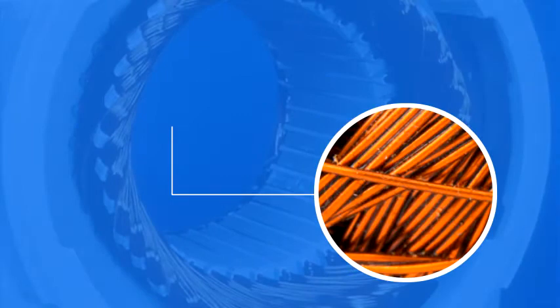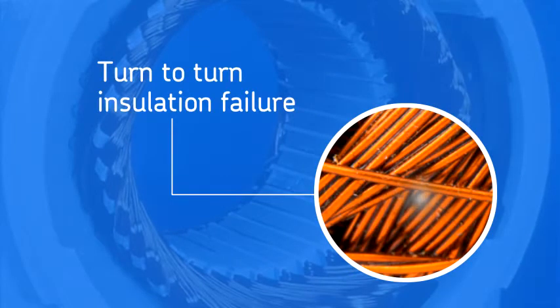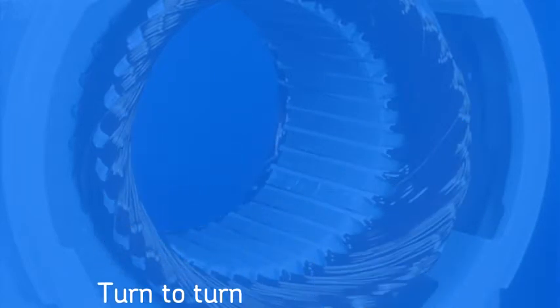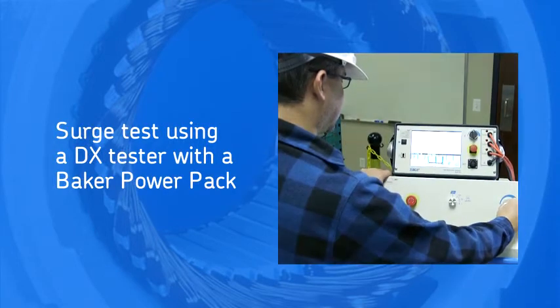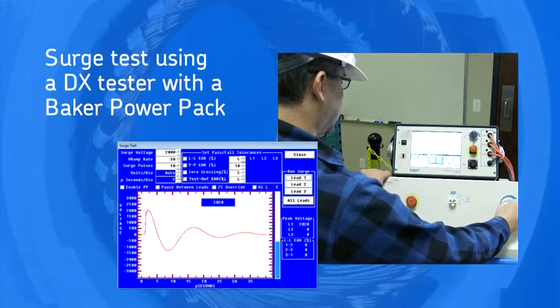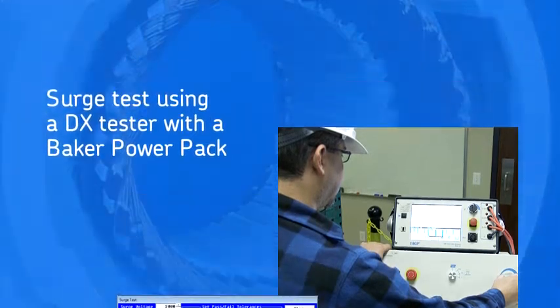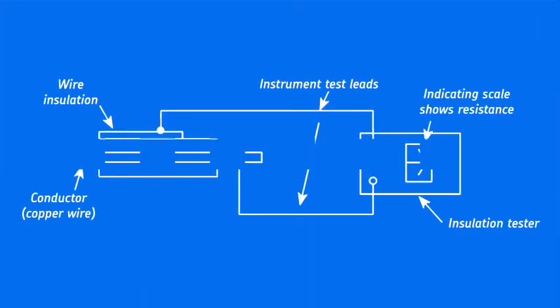The most common insulation fault is a turn-to-turn insulation failure. A surge test is the only test that can find turn-to-turn insulation weakness and failures.